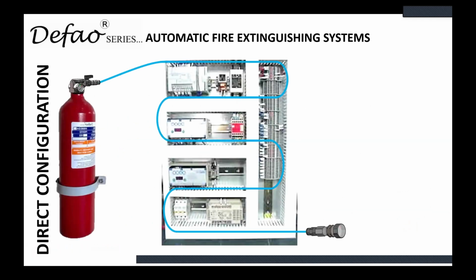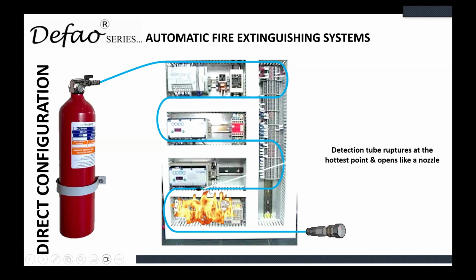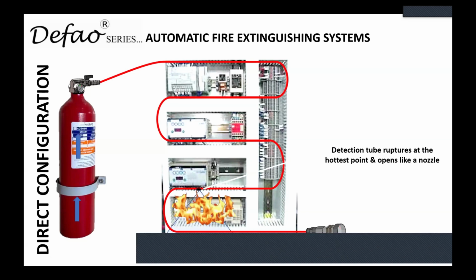For the benefit of the audience who don't know what the direct and indirect configurations are, this is a mock-up of a direct configuration where we have the cylinder which is filled with an extinguishing agent. Here we have the valve, and a blue colored tube is running inside the electrical panel we are going to protect. The blue indicates that the line is pressurized with nitrogen. So in case there is a fire, there is a puncture that happens at the source. Instantaneously, the pressure difference in the tube causes the valve to open and the cylinder contents are discharged directly onto the fire source. The detection tube ruptures at the hottest point and opens like a nozzle.